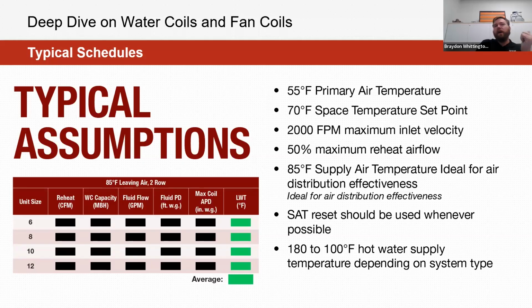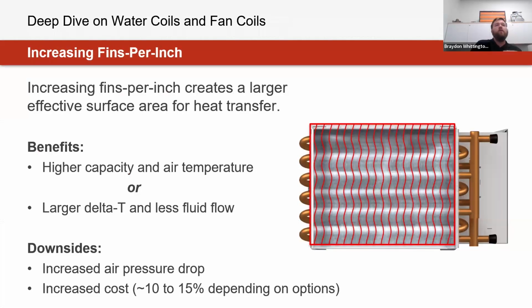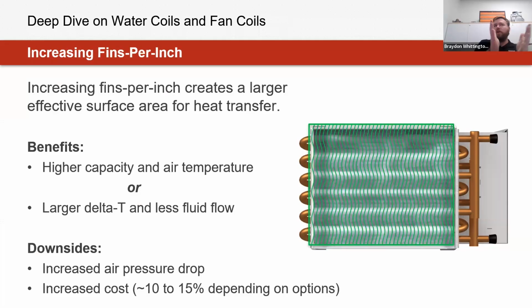So for the most common sizes of single duct, we're going to be playing around with different water supplies entering them, but with very typical entering conditions in terms of a velocity profile for our reheat flows, and also our entering air conditions, and just playing around with 2-row coils here. The first option for allowing additional heat transfer from the coil is high capacity coil options, or increasing that range. Where we'll see this for fan coils is for high performance fan coils, as well as maybe some of those commodity types that you would see from the windowsill, increasing to a 12 or 14 inch, just to allow for a higher level of heat transfer coming from the coil itself. From a VAV perspective, it's bumping from 10 to 12 fins per inch, just to try to achieve a certain leaving air temperature coming from that coil as well.